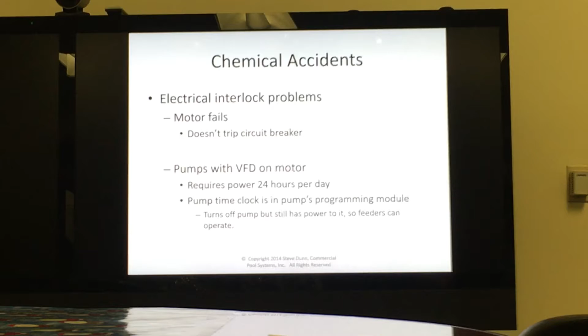So what's happening here is you've got your power source coming in, as you can see. And then you've got two relays inside here. One would be for chlorine and one for ORP. I mean, one for pH and one for ORP. So if, as opposed to interlocking electrically with the motor, with the pump, you use a flow switch. So if there's no flow, your chemical feed's not on. But when there is flow, you've got chemical feed. The flow stops, it's off.